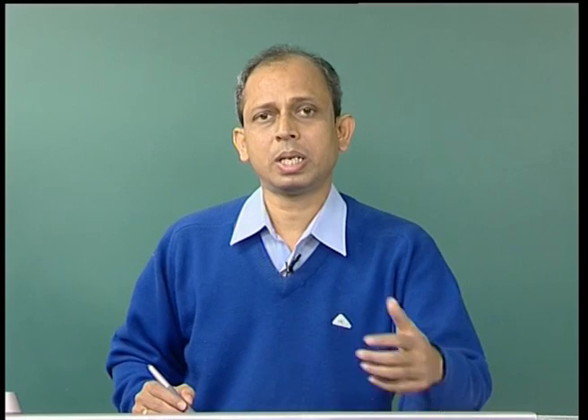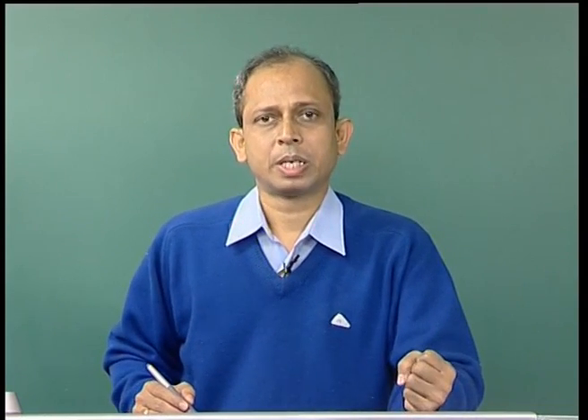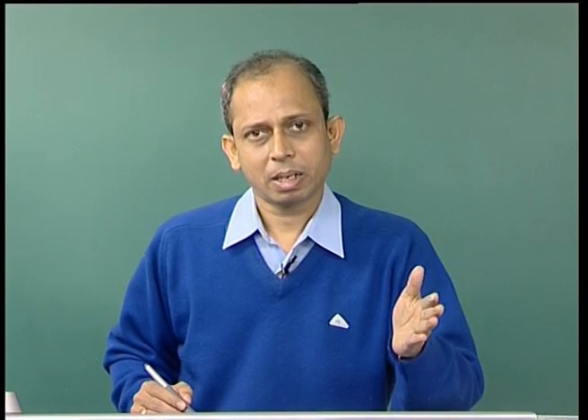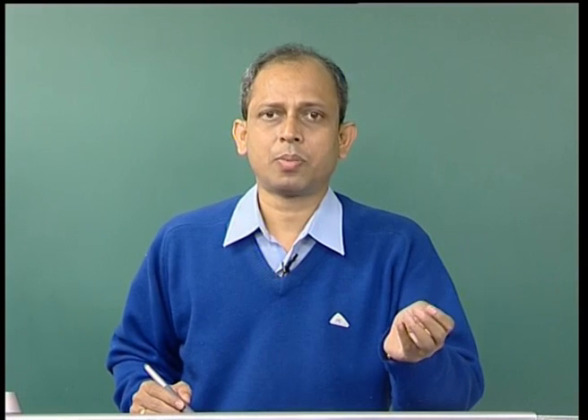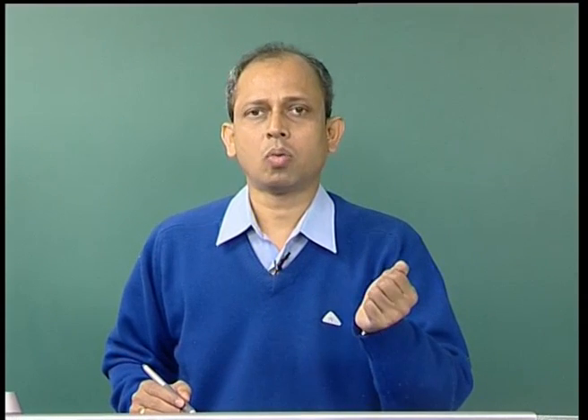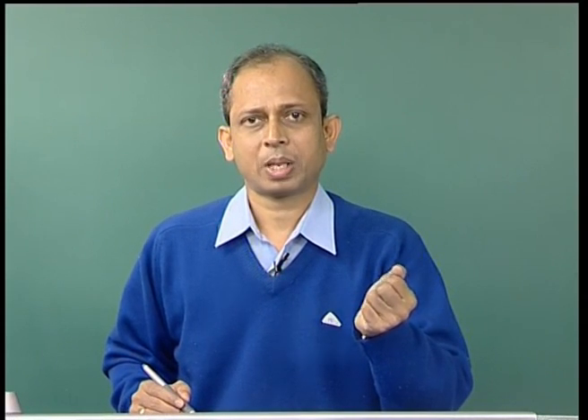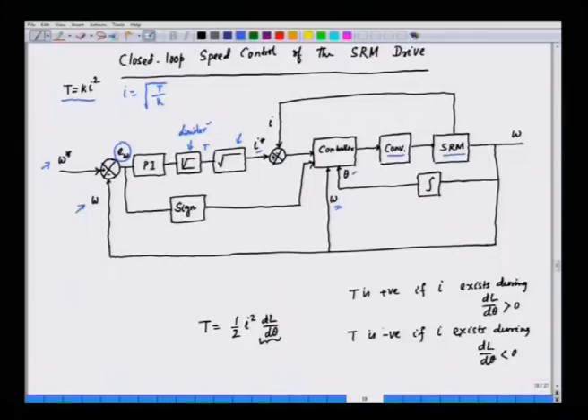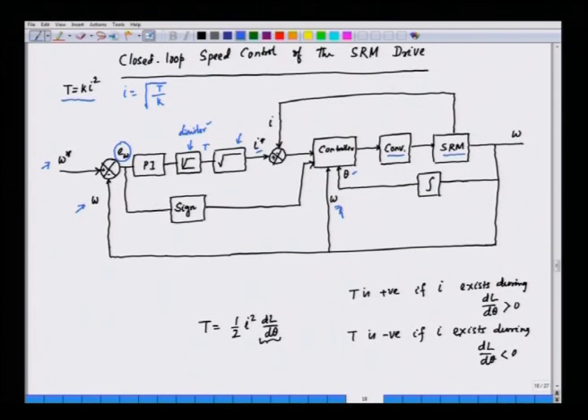The current I* is injected into the SRM by means of a converter, and the controller decides the switching angle depending upon theta. The SRM can be operated at very low speed in chop mode, then after the base speed it operates with constant power, and beyond some speed we go for T·omega² = constant. These are the various modes of operation, decided based on speed. The speed is also fed as input to the controller to decide the mode of operation, and we have a speed sensor for closed-loop speed control.